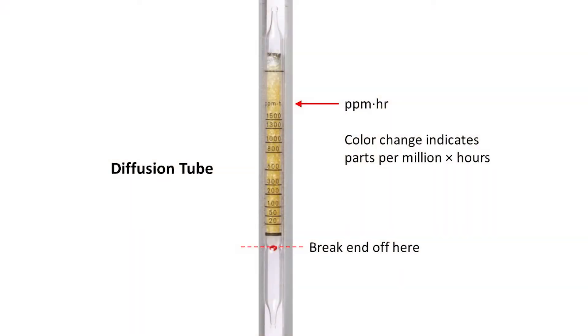A diffusion tube gathers information over two to ten hours in concentration time units of ppm hour or parts per million times hours. A scale is provided on the side of the tube for the direct reading.